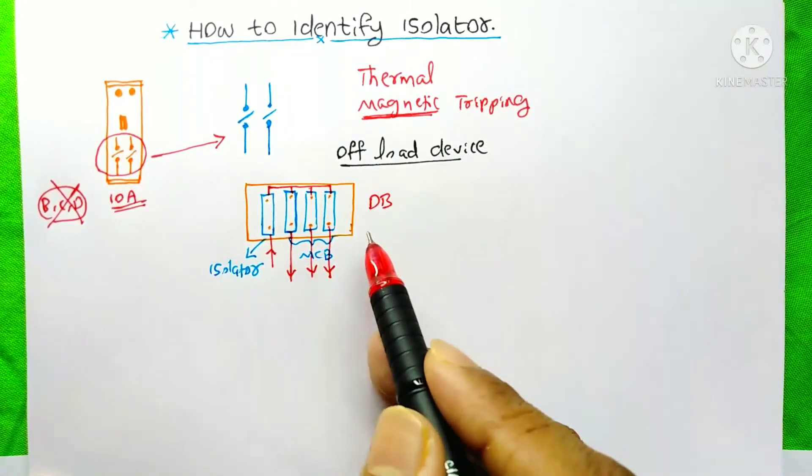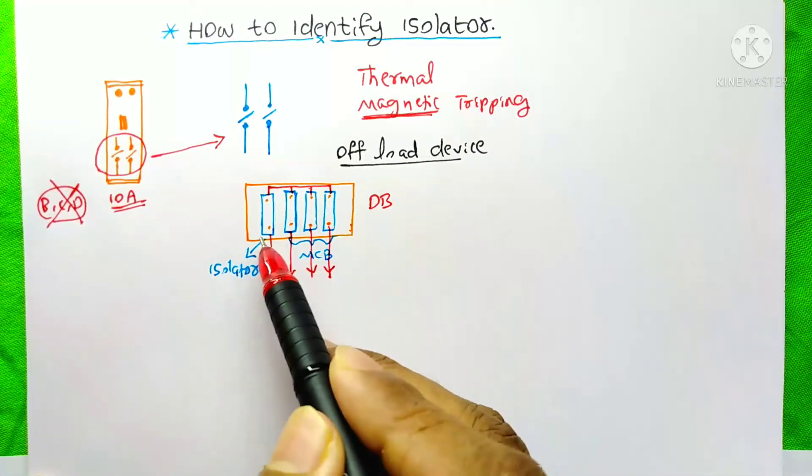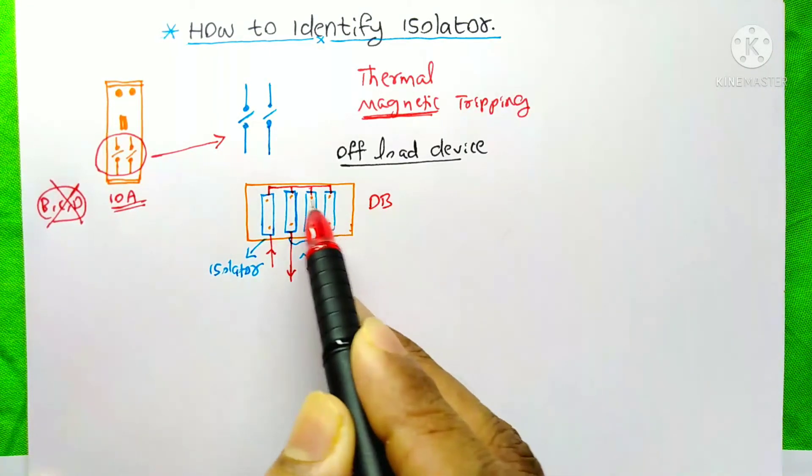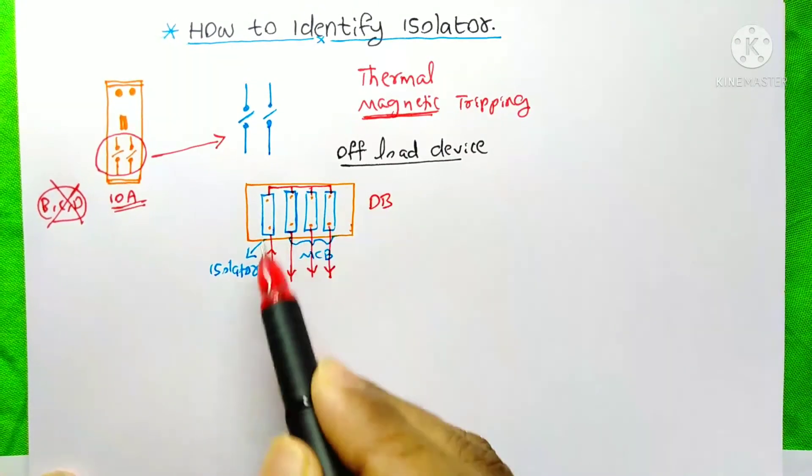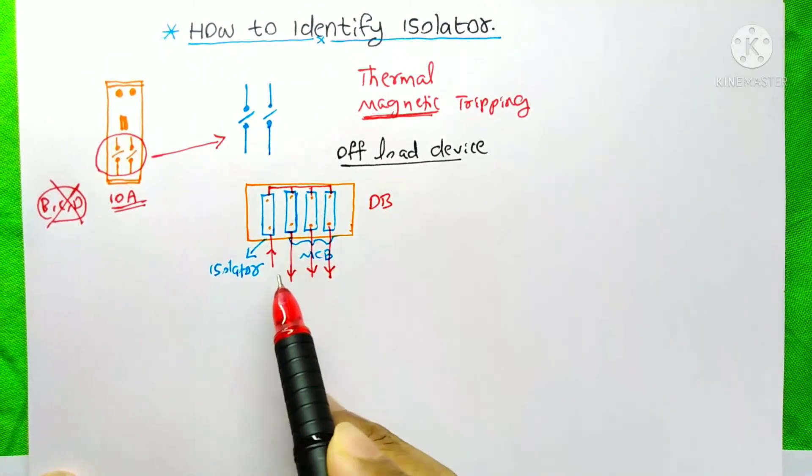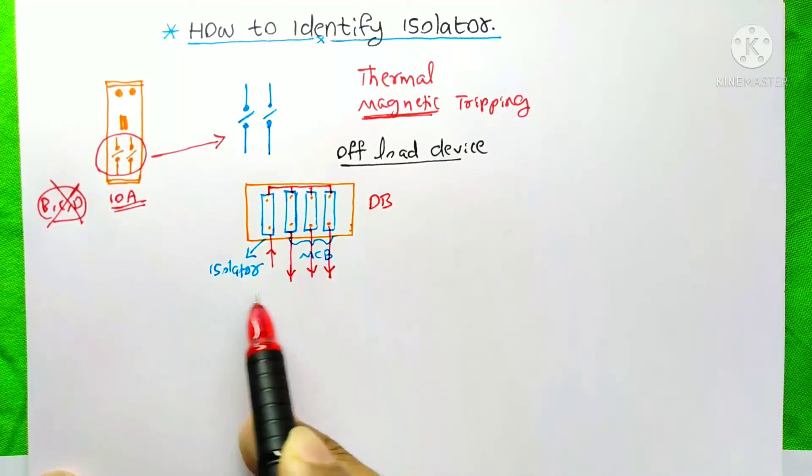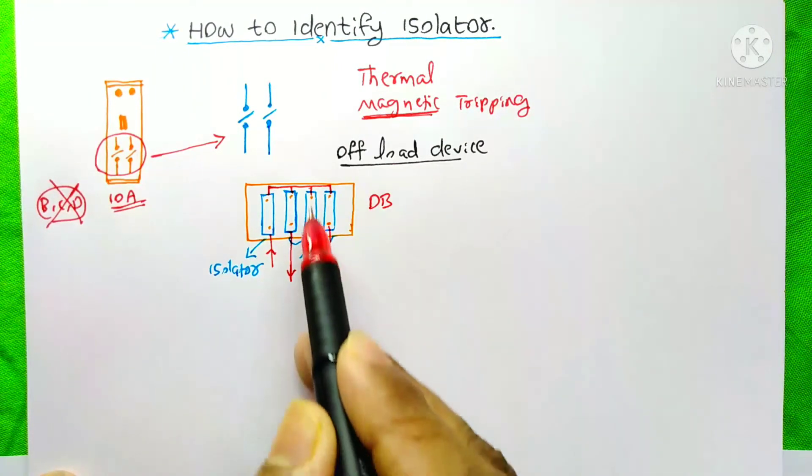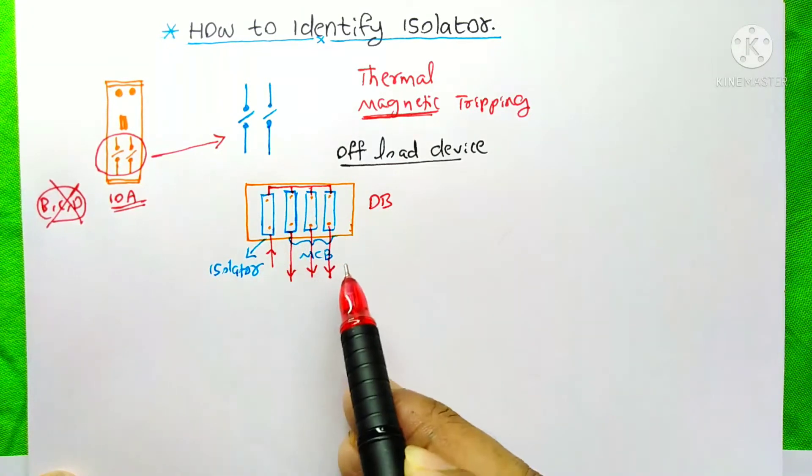See here I just showed a DB distribution board. And in this DB it is our main isolator and after that I just showed the three MCBs. If the loads are running now that means the current is passing through the circuit. And in any condition if you want to switch off this isolator, first you need to switch off all these MCBs and make sure that your loads are off.